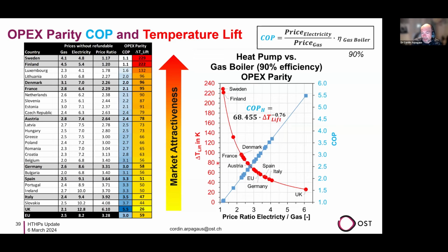This means if we have 40 degrees waste heat and an 80 Kelvin lift, giving 120 degree supply - so low pressure steam - with 40 degrees waste heat would be economic. If the price ratio goes further down, even 100 Kelvin lift gets economic. So it's an illustration of how this is all related.